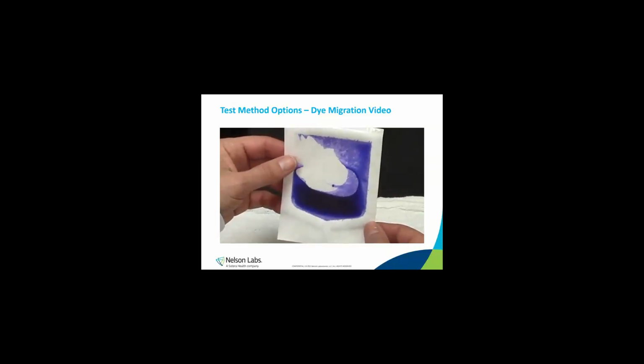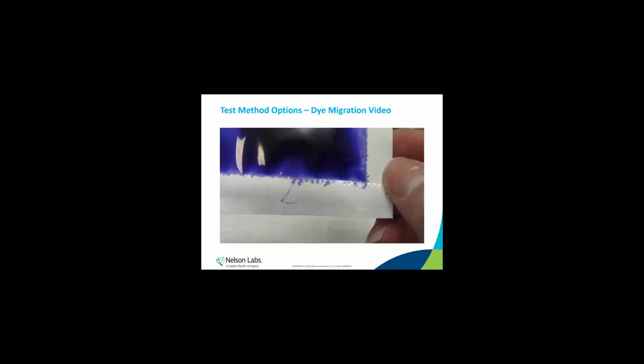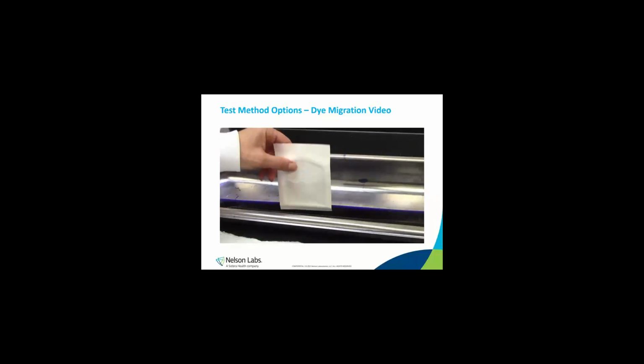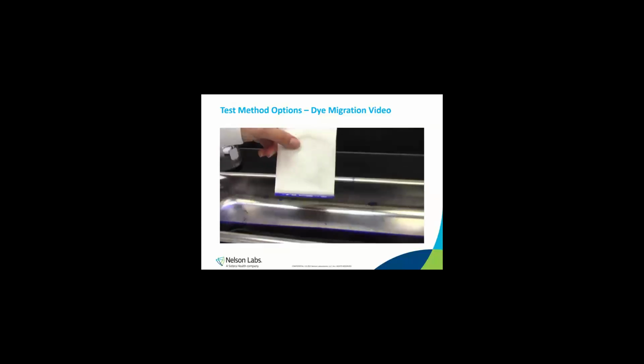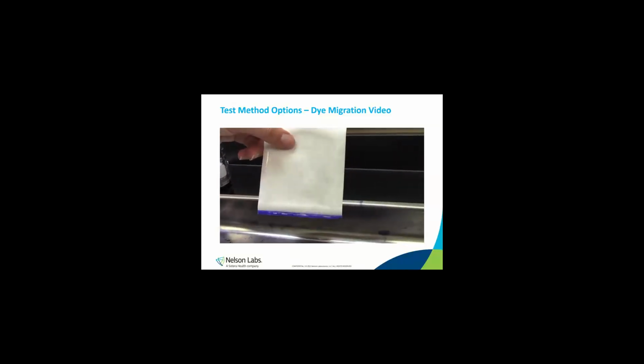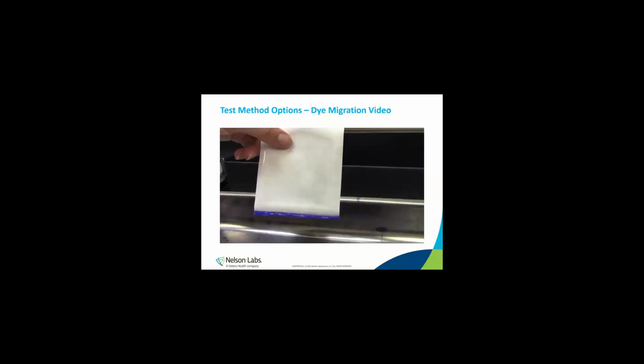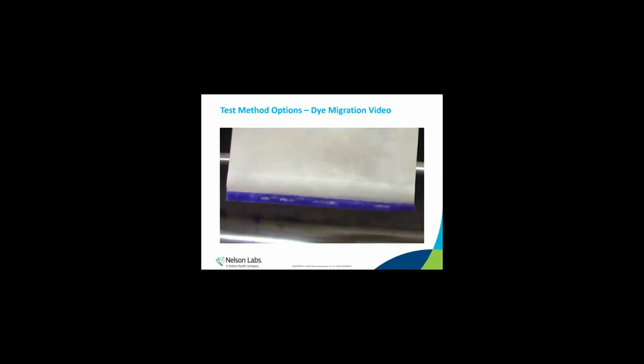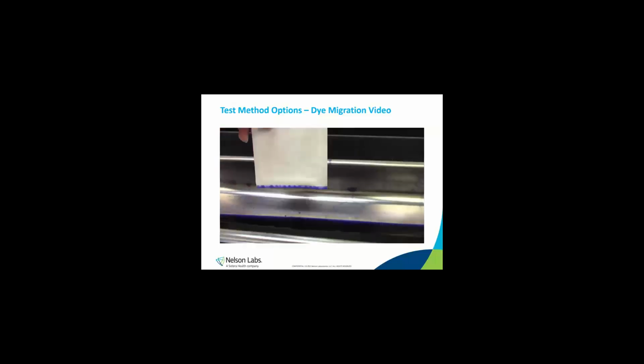Okay, here's an example of a good seal, and this is a channel. That's a 50 micron wire. If we're doing the edge dip, we just dip the edge of the sample into the dye, we pull it out and look at it. This one here is a good seal. And here's, look how fast this channel appears.